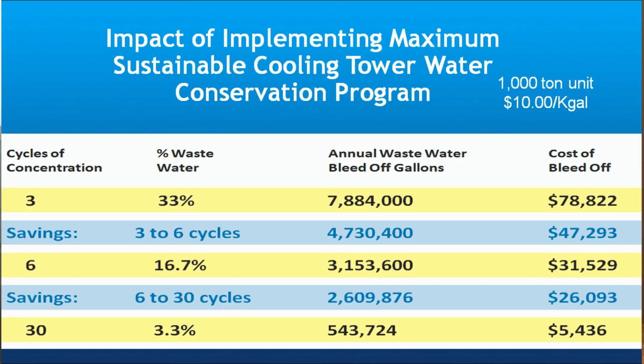The emerging technology utilized in these case studies and what is being implemented on more and more cooling towers effectively and safely increases cycles of concentration to 30 cycles of concentration, while maintaining complete system integrity. This slide shows the impact this can have on just one 1,000-ton unit with water sewer costs of $10 per 1,000 gallons, with a typical ROI of less than 12 months. As you can see, there is significant savings in both water and money well beyond three cycles of concentration.